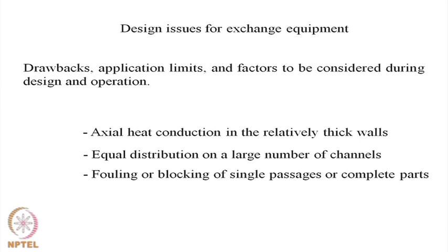And another important thing that I haven't spoken about before is fouling or blocking of a single passage or complete parts. It's not possible in most cases to clean a microchannel once it gets fouled or blocked by the presence of suspended particles. So, these are some of the issues that one has to keep in mind during design and operation.